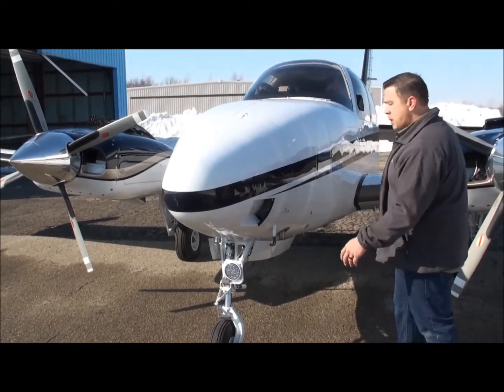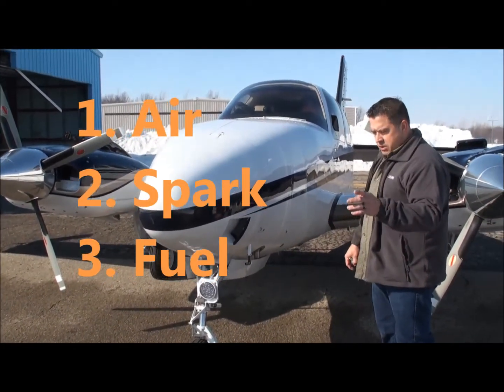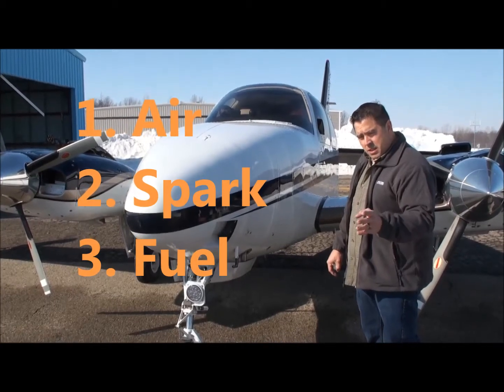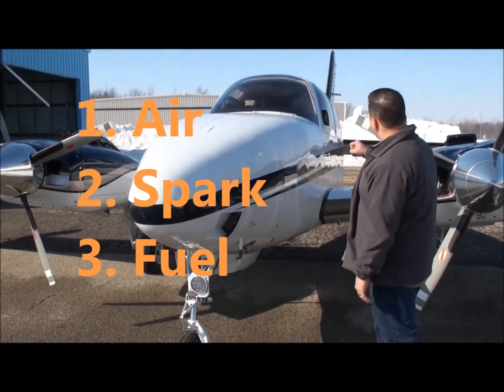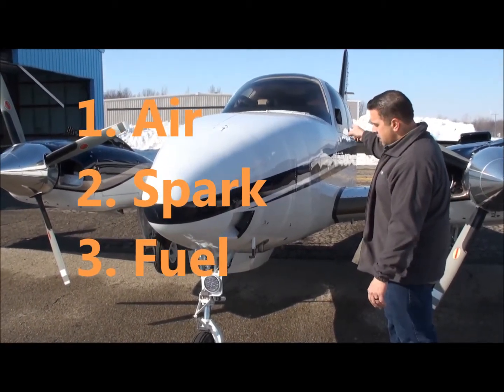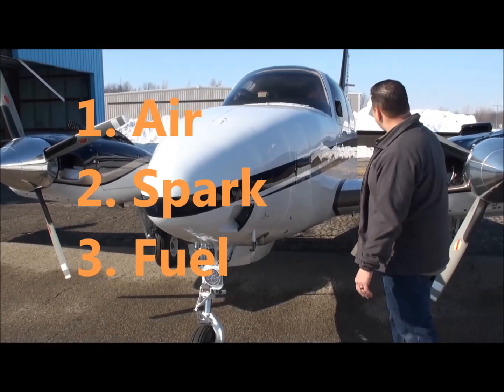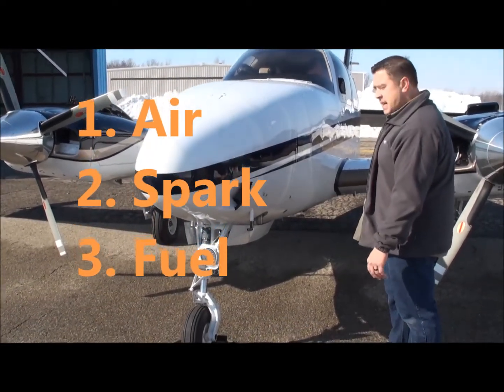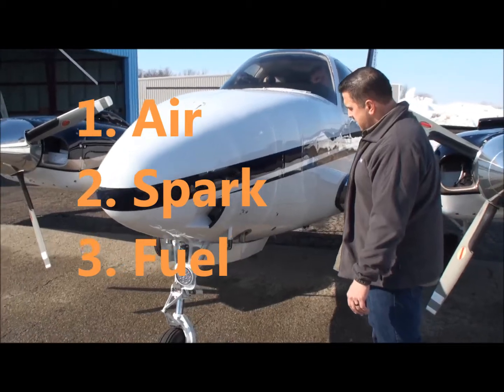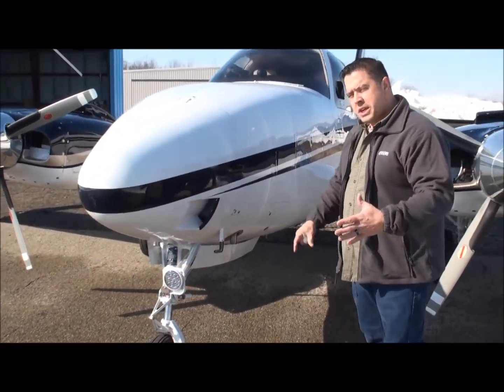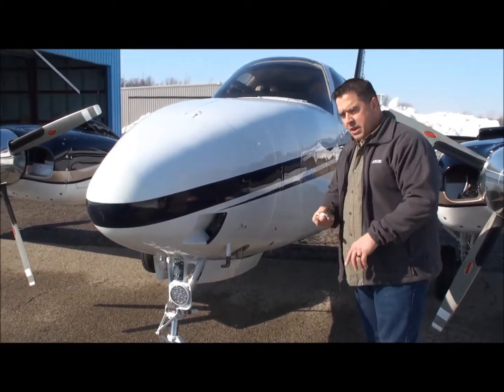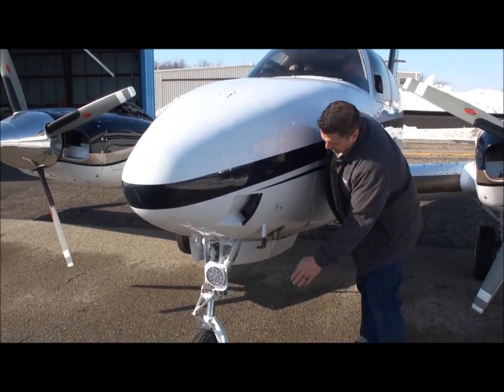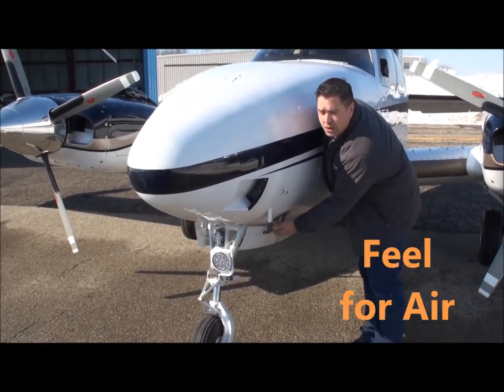So we're going to go ahead and look for air, then we're going to look for spark, and then we're going to smell for fuel. So we'll have our operator start the heater on low. Thermostat to low, you're on. And we're just using our senses. We're using a sense of smell, hearing, and feel.